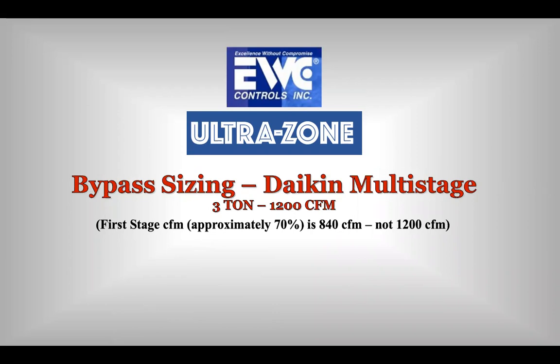Now, quite often people believe that once I get into this communicating equipment, whether it be multi-stage or modulating inverter, that I don't need a bypass anymore. The straight down and dirty is my lowest fan operating speed in a multi-stage system, a two-stage system, is 70%. That means no zone could be smaller than 70% if you did not want to use a bypass. Otherwise, I've got excess air that I'm not getting rid of, and I've got static issues, and I've got noise.